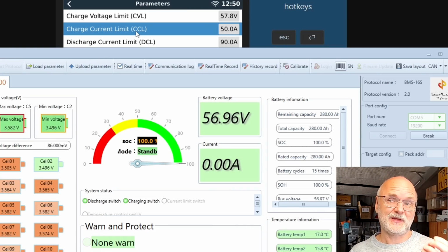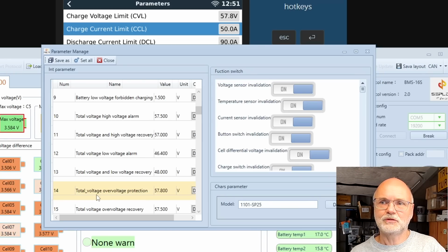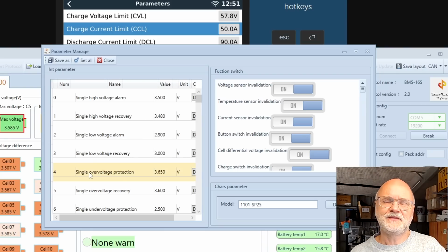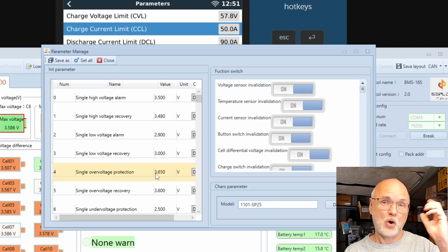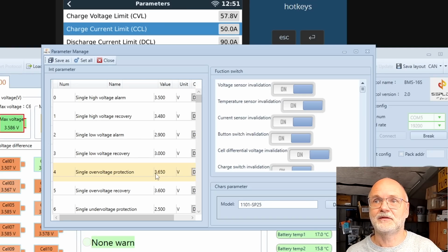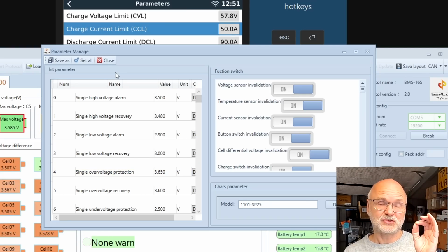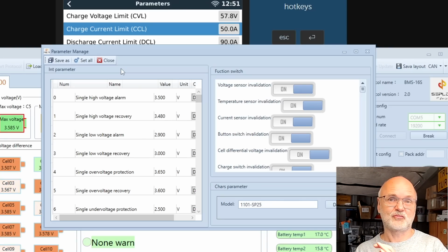And this was, as per Seplos information, the only way to reset your BMS to 100%. So either hitting the total voltage over voltage protection, number 14, or number 4, single over voltage protection, which is at 3.65 volts — either cell or pack over voltage protection resets to 100%. This was the written information I got from Seplos. I have tested it, and it worked, and I couldn't find any other way to reset to 100% until now.